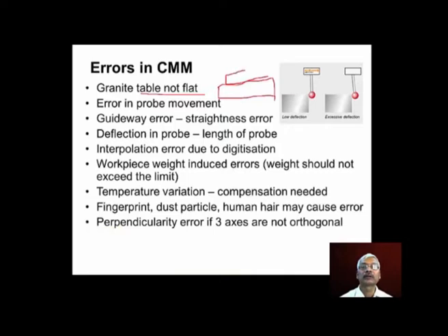So it will rest on the table at some inclination. Because of this, errors will be introduced. And error in probe movement, that means when the probe moves in the X, Y, Z direction, there is some error in the guideway. The guideways may not be straight, or they may not be moving along a straight path. Because of this, there will be error in the measurement.